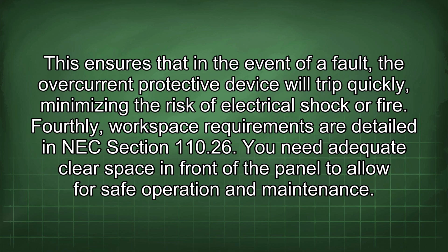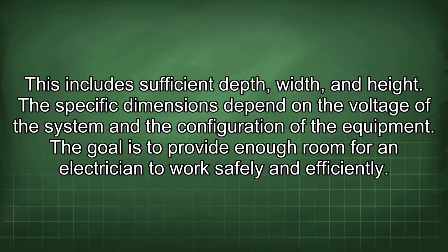Fourthly, workspace requirements are detailed in NEC Section 110.26. You need adequate clear space in front of the panel to allow for safe operation and maintenance. This includes sufficient depth, width, and height. The specific dimensions depend on the voltage of the system and the configuration of the equipment. The goal is to provide enough room for an electrician to work safely and efficiently.